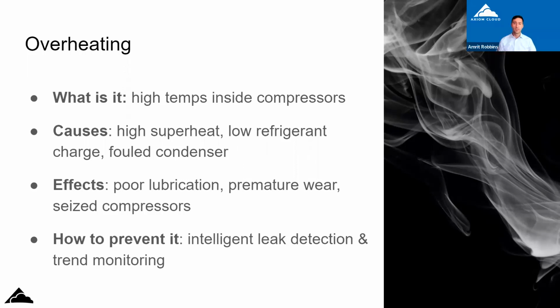So step one is make sure you have the right sensors. Step two is make sure the technicians can access the data. And step three is make sure they actually understand what they're looking at. Yeah. For example, Bitzer has something called the IQ module. It may even hook up to Axiom Cloud, but it does everything: you can do your suction temperature, your discharge temperature, your pressures. Copeland has the CoreSense diagnostics for semi-hermetics, or CoreSense protection. It does the same thing, oil pressure, all the stuff. It does it all. But at the end of the day, if someone just keeps pressing the oil reset button or the alarm reset button, it's not going to protect the compressor.